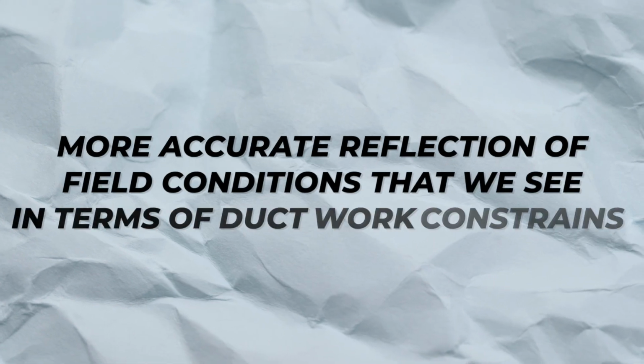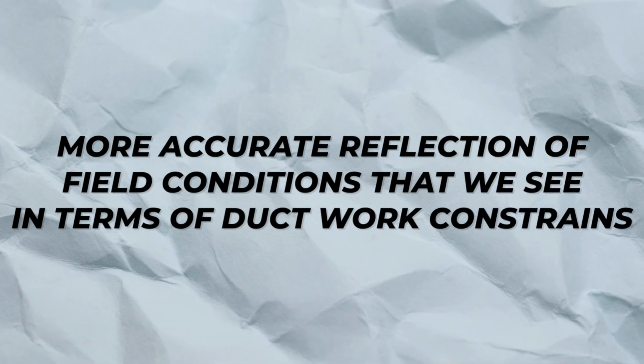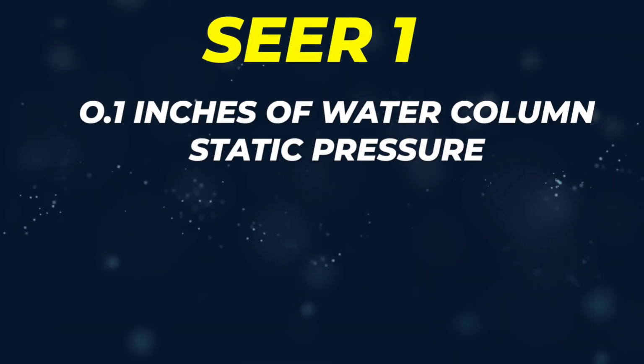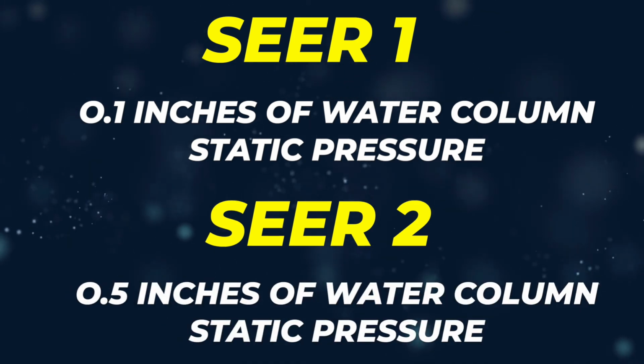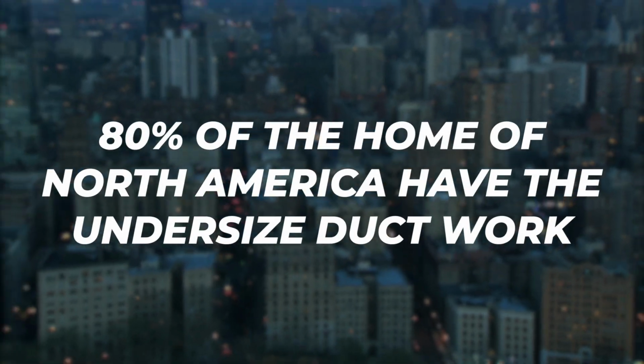It's a more accurate reflection of field conditions we see in terms of ductwork constraints. SEER 1 was based on 0.1 inches of water column static pressure, whereas SEER 2 is based on 0.5 inches. That means it's a more accurate reflection of how efficient a system is when we actually install it in someone's home, because we never find homes with 0.1 inch water column static pressure — 80% of homes in North America have undersized ductwork.